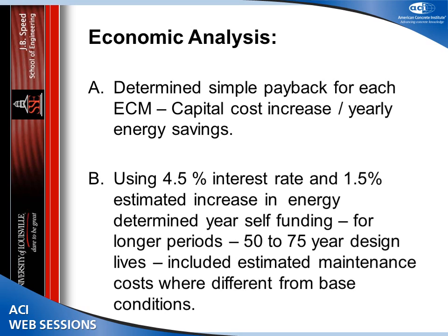We looked at, first of all, simple payback, taking the energy costs that we saved, the yearly energy savings, compared that against the actual cost of the ECM, and we calculated a simple payback. We also looked at around 4.5% interest rate and about a 1.5% estimated increase in energy costs.